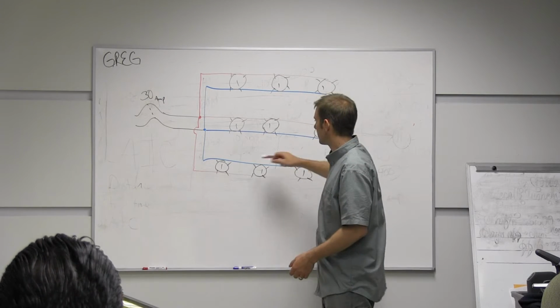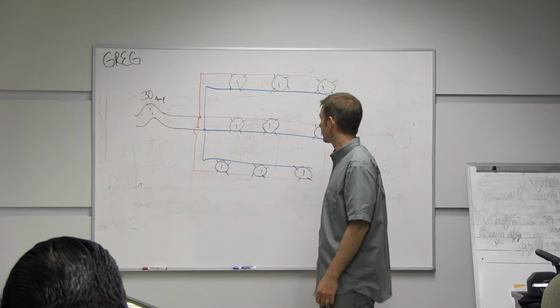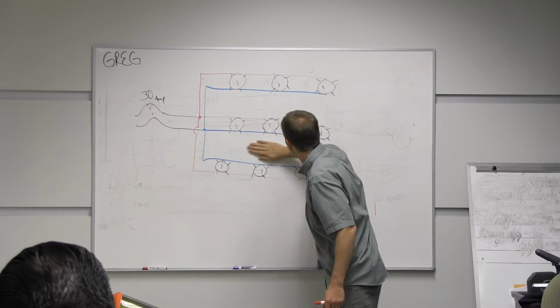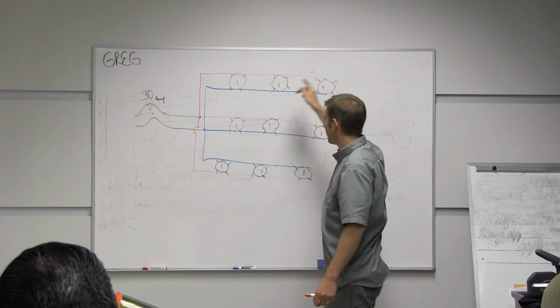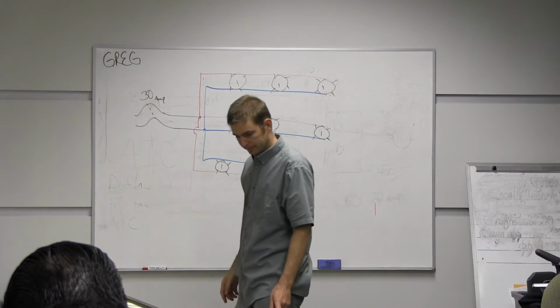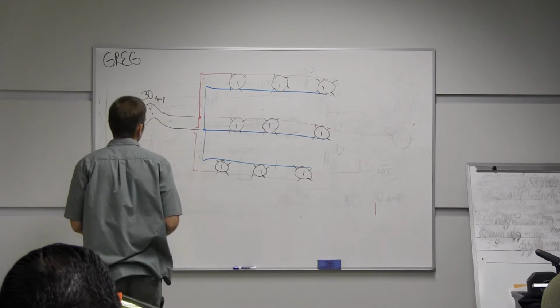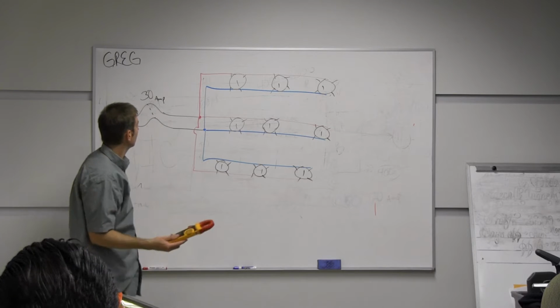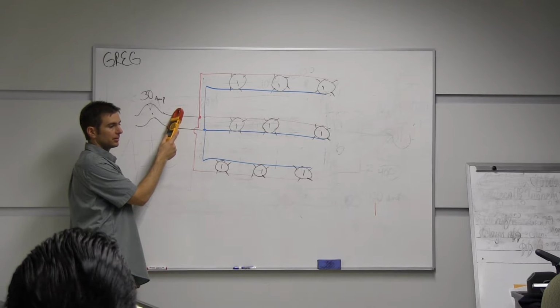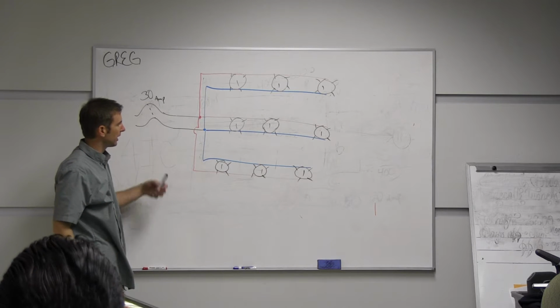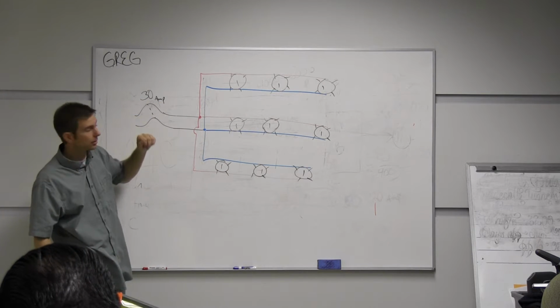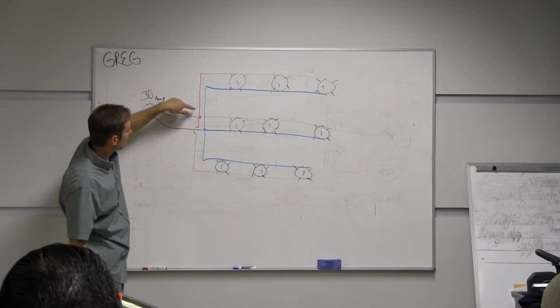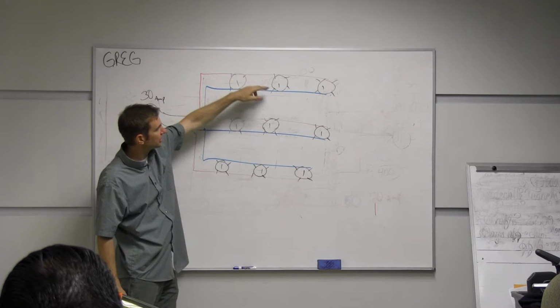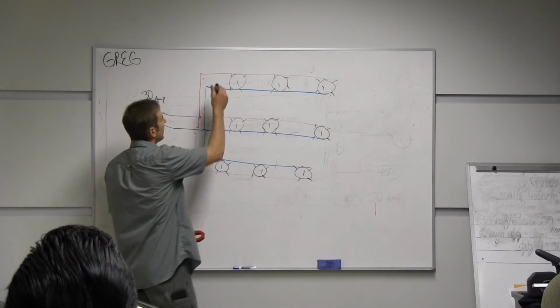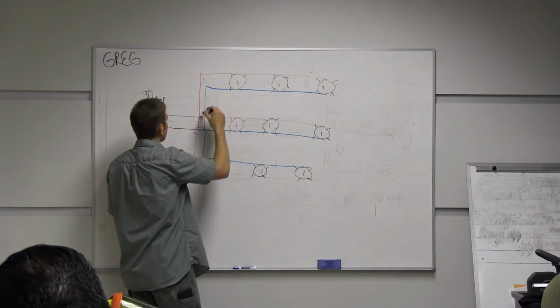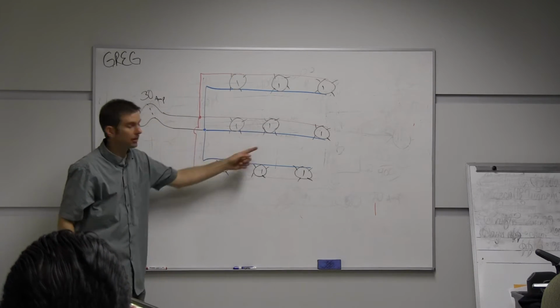All right, so we have 9 lights. Each one of these is a light fixture. I know there's a background drawing you can see here, which makes it harder to see. I probably should have cleaned this up a little bit better. So I have 9 lights. Each one of these is drawing 1 amp. I have a 30 amp circuit breaker. How many amps do I have? 9. I have 9 lights. They're all carrying 1 amp. They're 240 volt, so I have 2 hot wires going out, the red wire and the blue wire. The red wire touches each one, and the blue wire touches each one. 1 amp goes to this light, jumps over to this blue wire, and then comes back here. And that happens to each of these lights.